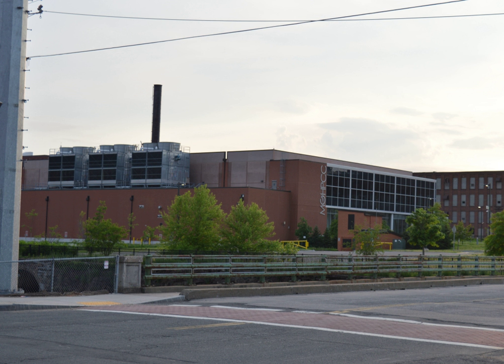The MGHPCC shares the 34.5 kV bus exclusively with the Hadley Falls Hydroelectric Station, the largest of HG&E's hydro facilities, which creates a direct power path to the computing center from the Hadley Falls plant.